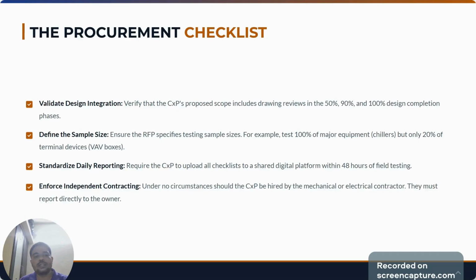Now, the best practice checklist. As a wrap up, here are 4 simple golden rules for your next project checklist. One, make sure the CXP contract includes drawing reviews during the design phase. Two, specify the sample size - for example, tell them to test 100% of major equipment like boilers, but only 20% of smaller devices like office thermostats. Three, enforce digital reporting so you can see their progress in real time. And fourth, most important, never let the general contractor hire the CXP - the CXP is your independent auditor, and they must report directly to you to ensure total honesty.